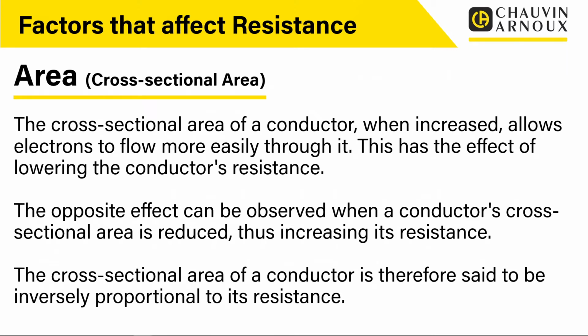And this is a factor that can actually be seen specifically when we're measuring, say, the contact resistance of a relay, and you might have a tiny little bit of the contact that's actually touching rather than the whole surface. What you'll find is that's shown by the fact that we've got a reduced cross-sectional area. We should have the whole contact touching, but we've only got a tiny spot that's touching. That tiny spot is a reduced cross-sectional area, and that would give us an increase in resistance.